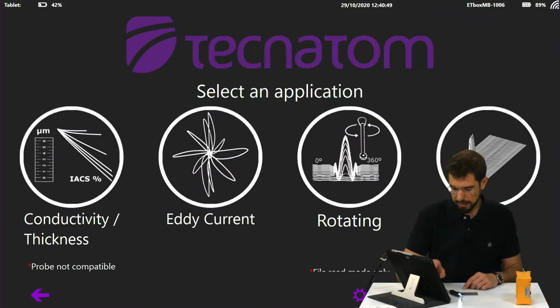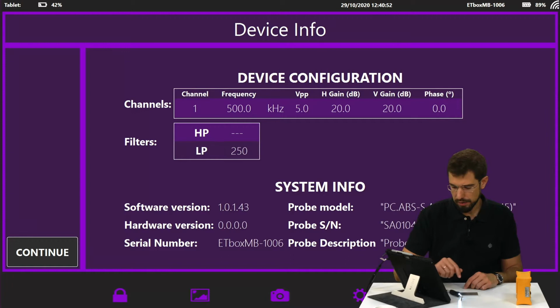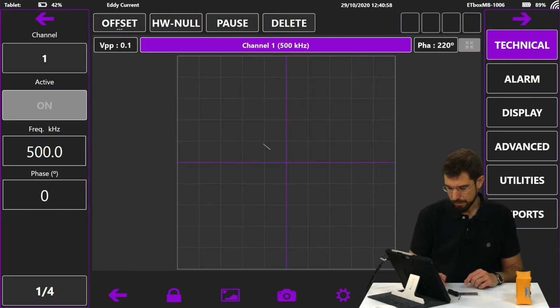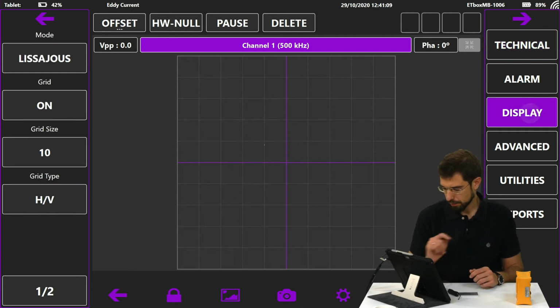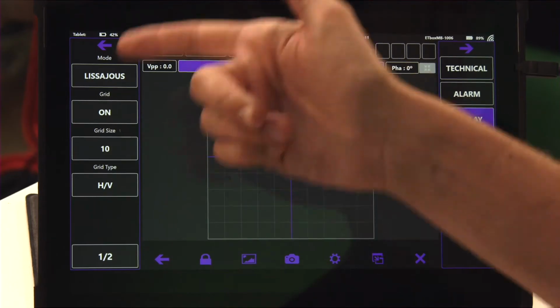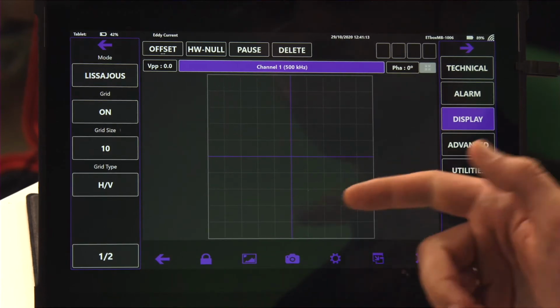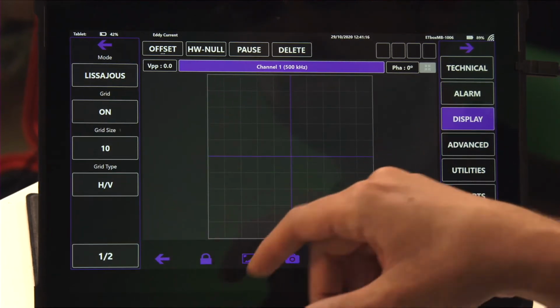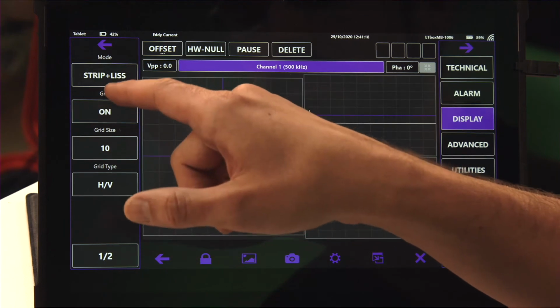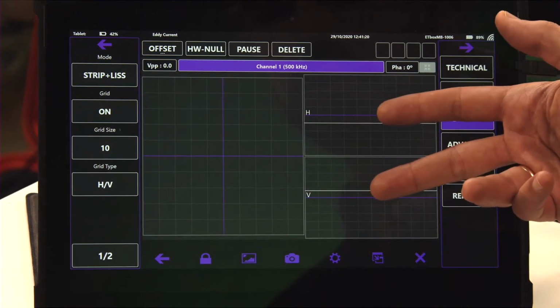We're going to start the Eddy Current application. It identifies our probe right away. Okay, so in this case, we've already seen the distribution of the screen. Let's configure the display the way we want it to perform our inspection. For that, we'll go to the Display menu where a sub-menu spreads out. We have a Lissajous open, and we're going to use Strip Chart with Lissajous.